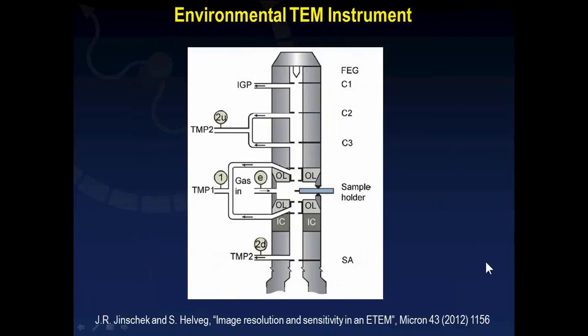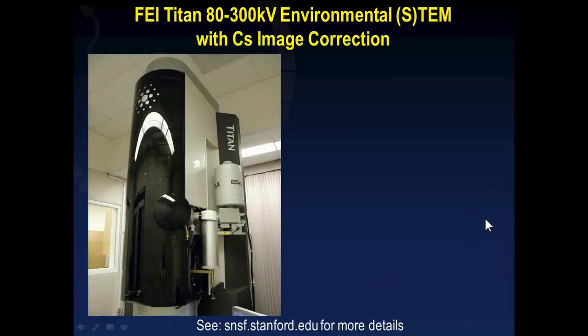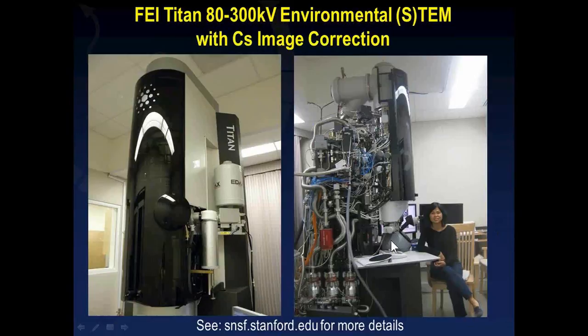The second approach involves a specialized environmental TEM instrument. In the ETEM, the objective pole pieces function as an environmental cell and gas is introduced within the objective lenses. Fixed apertures located inside the microscope column limit the volume of gas diffusing to other parts of the column such as the electron source. The gas is differentially pumped out of the column using a series of turbo-mechanical pumps. Our lab's ETEM has additional turbo pumps and lines which support the environmental mode of the instrument.